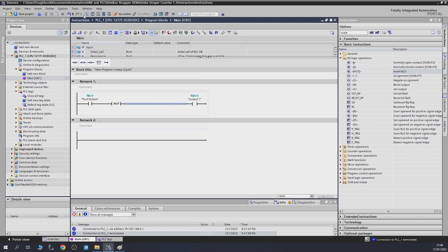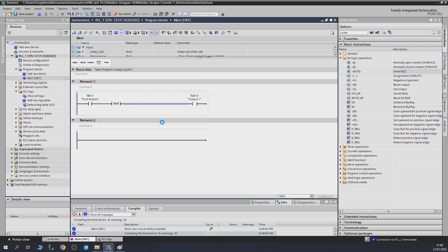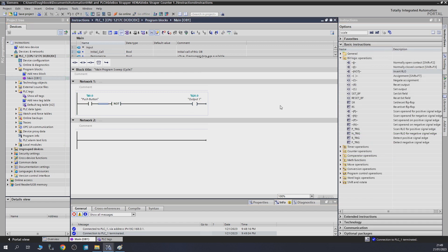Let's put NOT in there and compile and send it in. As you can see now, because of the NOT, the push button is not pushed but the output coil is on. What it does is invert anything past the NOT — anything there is going to be inverted. If I activate the push button, the signal comes to the NOT, the NOT inverts it and turns off the output. Turn the push button off and the NOT converts the output back to ON.